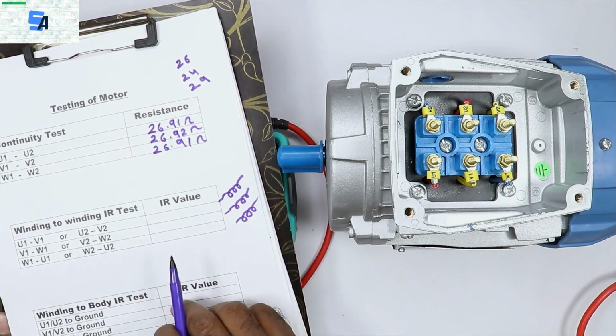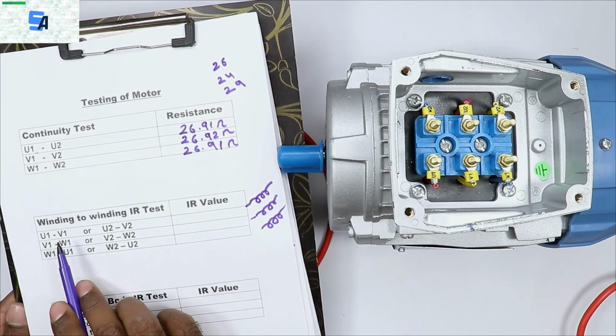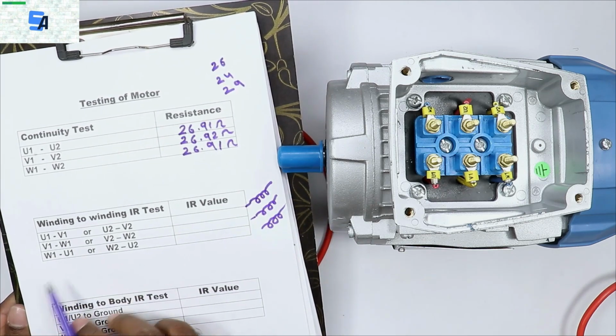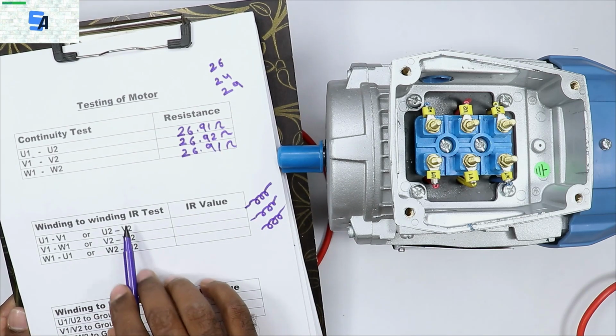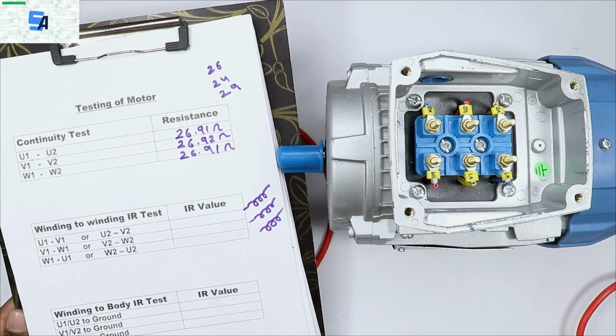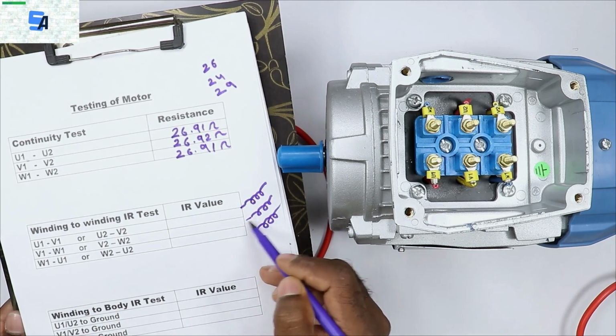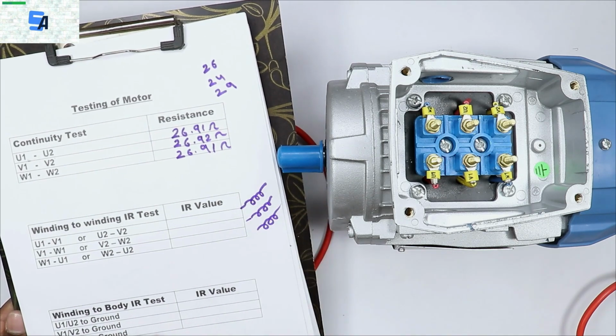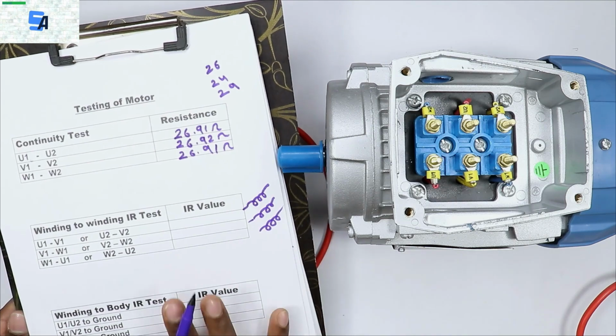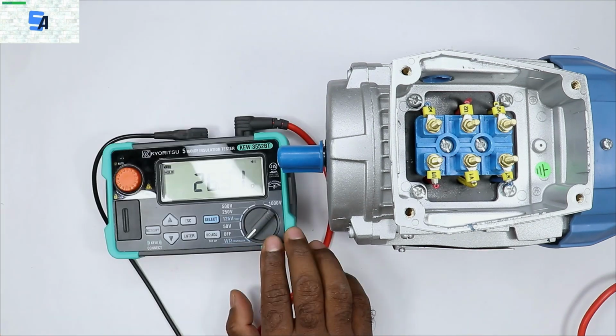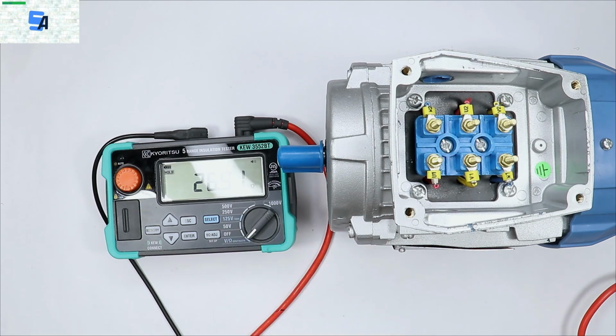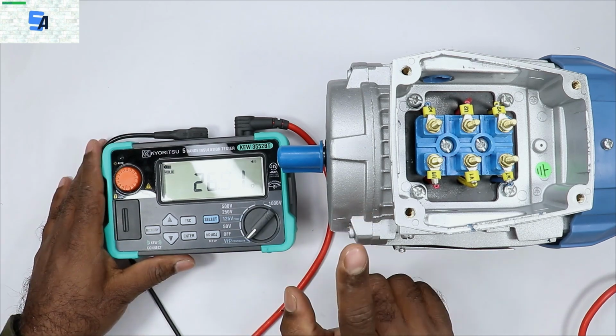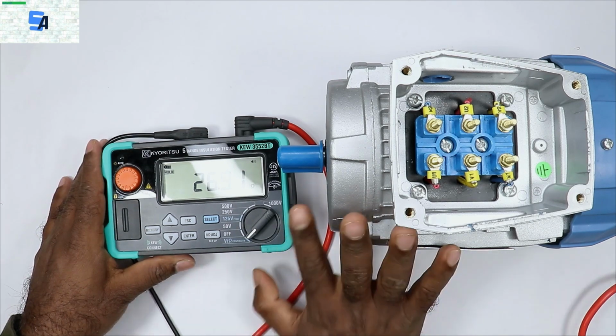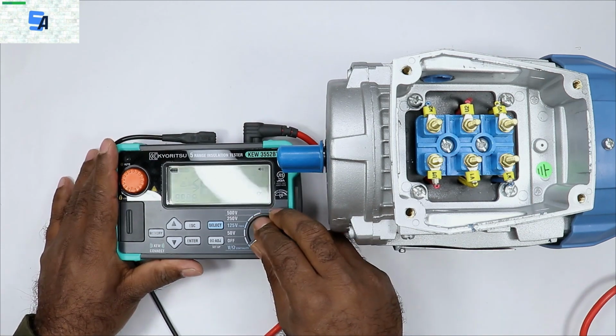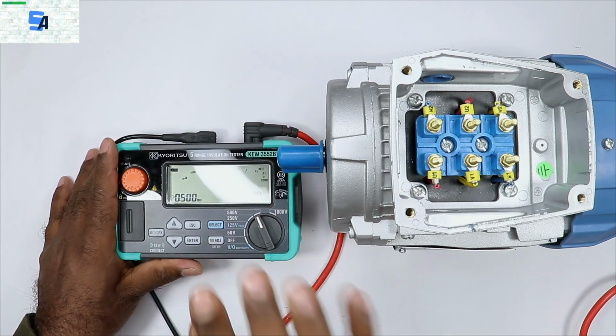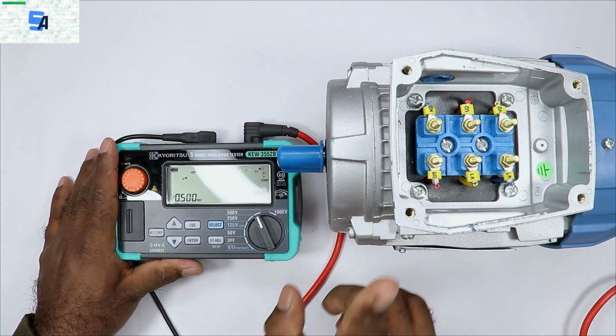To measure this, we will measure the IR value at the U1 terminal and V1 terminal, or if we want, between U2 and V2 also we can measure the IR value. It means we can measure the IR value here or here, and we will get the same value because the winding is the same. See, whenever you go for measuring the IR value, you have to select the voltage also. The motor I have has an operating voltage of 415 volts. In this condition, I will use the 500 volt position for measuring the IR value of this motor.